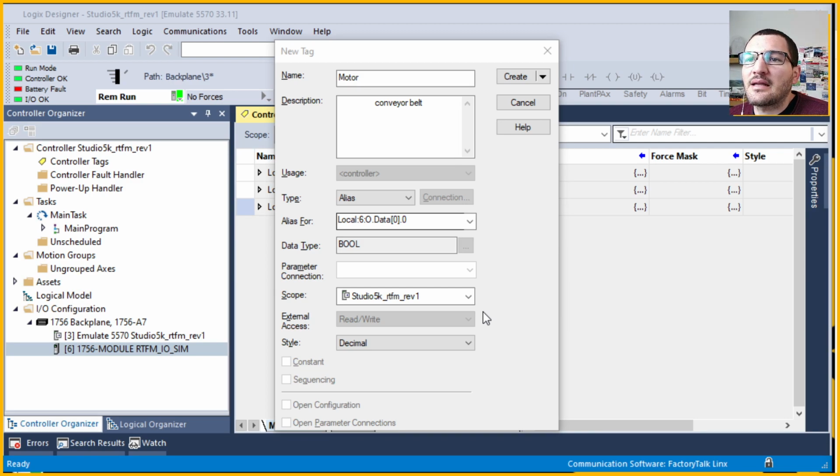If I remember correctly, back in the days, if you have a SCADA system talking to your ControlLogix, especially a third party, not a Rockwell one, you have to assign them all to controller level. I remember working with Wonderware InTouch. You have to have all the tags assigned at the controller level. Otherwise, SCADA wouldn't be able to pick up the comms and read and monitor that tag.